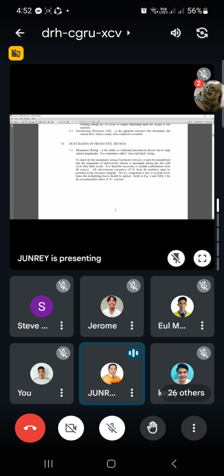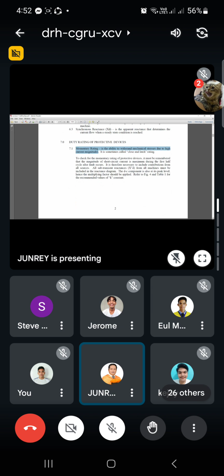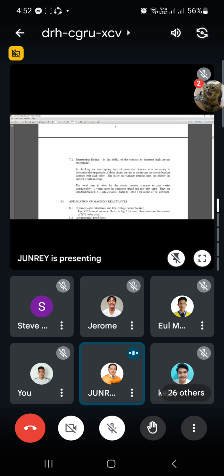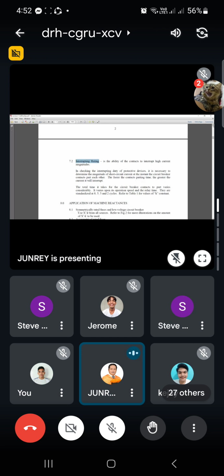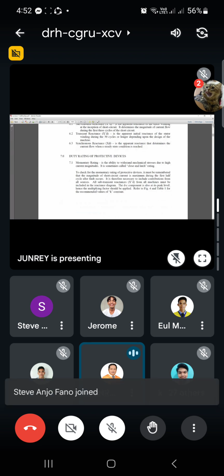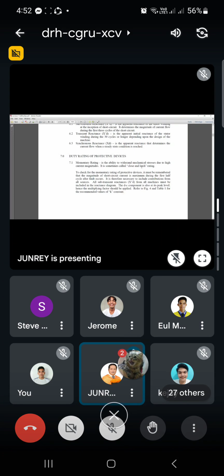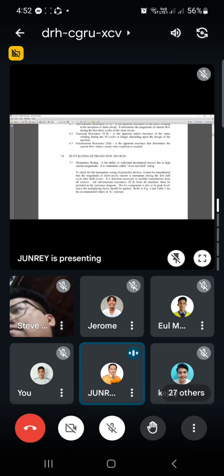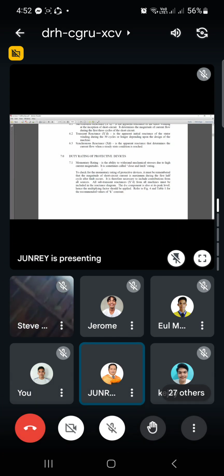So, duty rating of protective devices. Natay gitawag og momentary rating o interrupting rating. Silang duha. So, unsa may difference ang duha, si momentary rating o si interrupting rating? So, momentary rating, this is the ability to withstand mechanical stresses due to high current magnitudes. It is also sometimes called the close and latch rating.